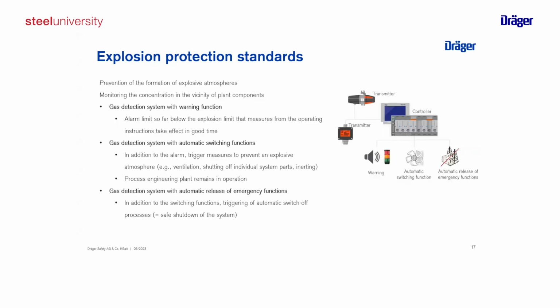If we are now looking at gas detection, so if we want to use a gas detection system for our primary explosion protection, then there are three types of gas detection systems. The first is just with a warning function. That means we have somewhere a sounder and a light which is activated in the case, and the operator needs to take measures, by having working instructions that people have to leave or that they have to switch valves manually. So this is just a warning.